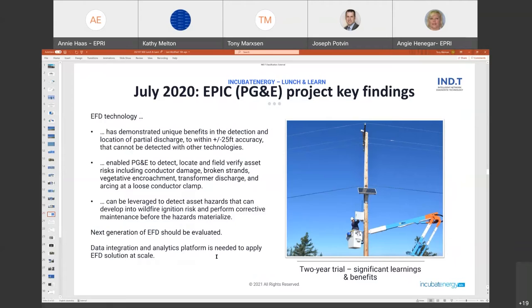Pacific Gas and Electric in California installed early fault detection on two circuits up in the Napa Valley area and operated them for quite a while. They did this project under their EPIC shared funding, shared R&D arrangements that apply in California.